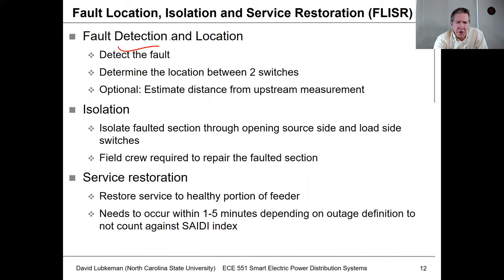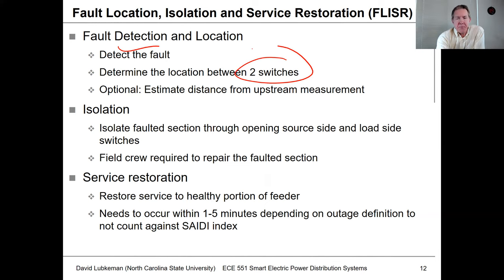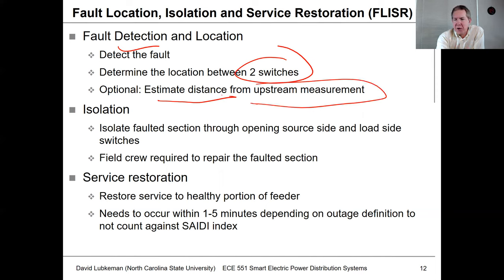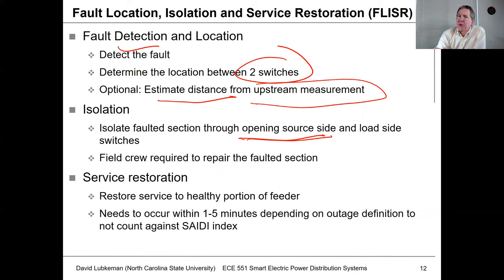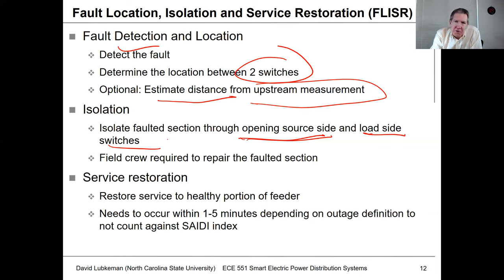The fault location part is really about detecting the fault first, and we like to get this between two switches. If I know the fault is between two switches, I can open those two switches and send crews to isolate that fault. Optionally, we can get the distance from an upstream measurement by running a fault location algorithm. The isolation step involves at least getting the switch opened on the source side of the fault, so I can restore sections above that open switch — and maybe on the load side as well.